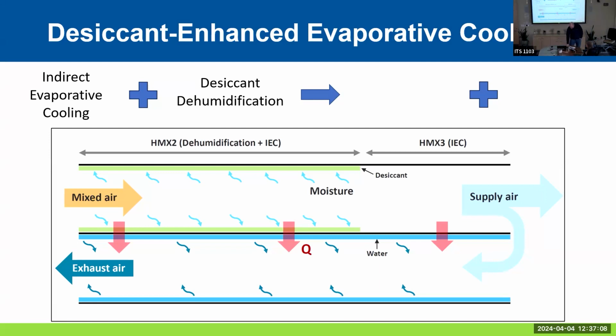If we follow the setup of the process, you have the mixed air - that's air coming from outside mixed with what's returning from the system. It goes through the beginning and encounters the desiccant, which pulls the moisture out. At the same time, it's pulling the heat out because the exhaust air is cool. Then you have the supply air that is dry and cool, and it can have any amount of moisture you want. This makes for efficient and robust cooling - we can cool and control the moisture based on the controls we set up for the system, and we can also save a lot of energy.